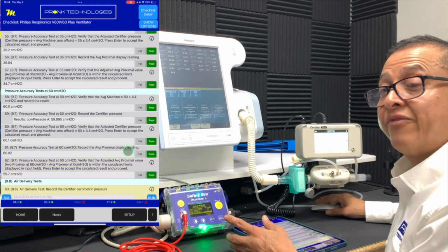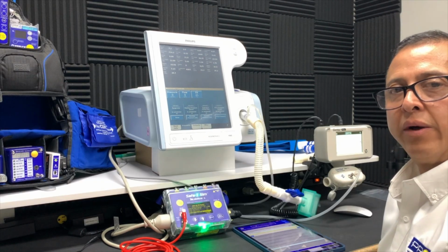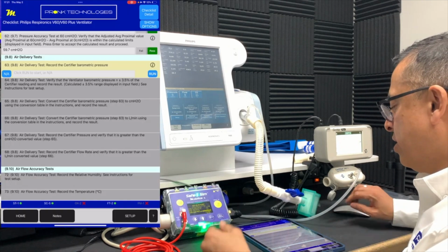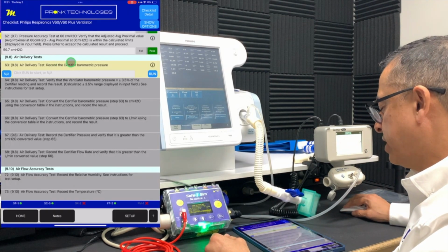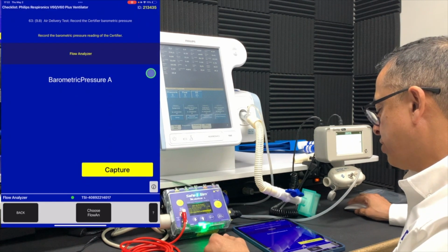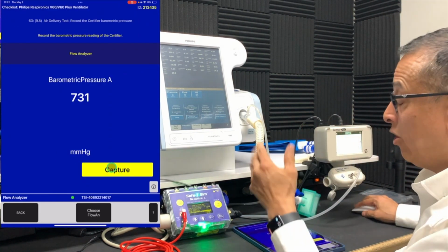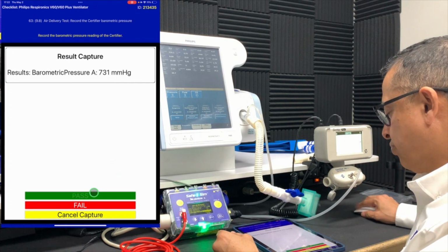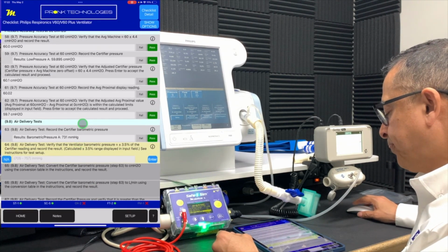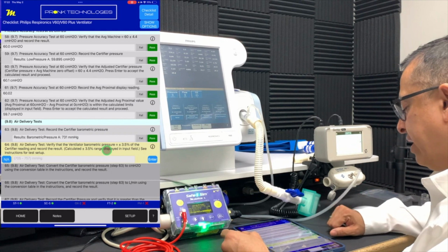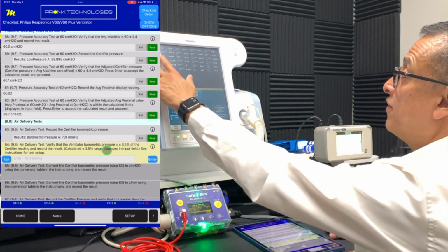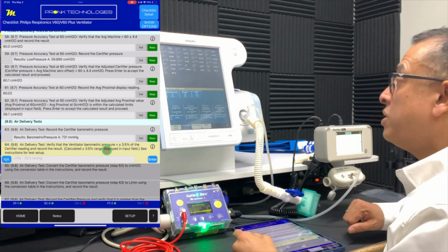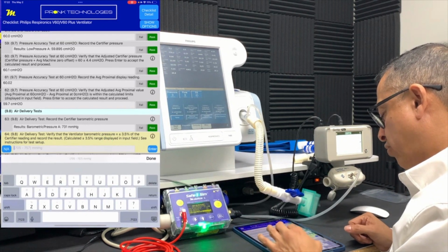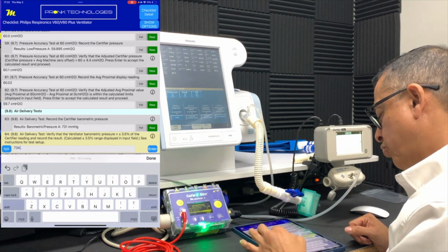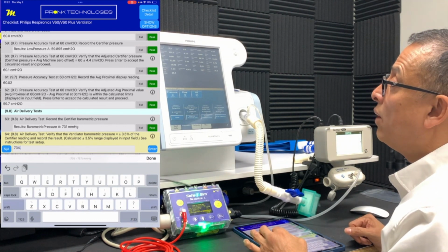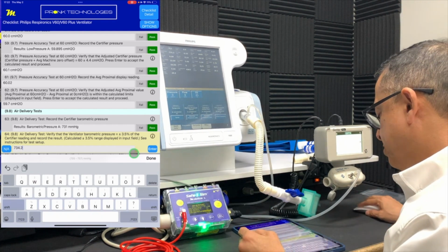Now we're ready to go on to the air delivery test. To start off with, we want to once again take the barometric pressure from the certifier. So we'll go ahead and do that in this next step here. You can see that's what we need to do. So we'll run that and capture that barometric pressure. Make sure it's within the tolerance allowable by the service manual to run these tests. We don't want to be outside of that barometric pressure range. And next, we want to verify that barometric pressure on the ventilator again and make sure it's within range of our specs required in the manual. And it's 734.2. We'll call it 0.2. We've captured that.